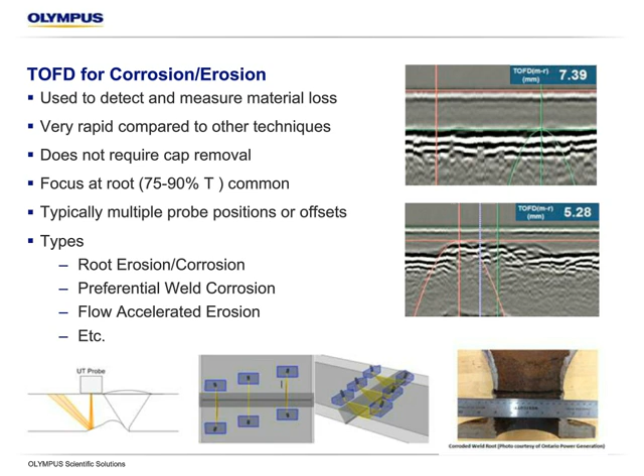So some things to consider when you look at TOFD equipment and what you need. Obviously, what techniques you're going to use, just TOFD or phased array. What channels are required? Do you need a single channel because you're only doing smaller thicknesses, or do you need multi-channels of TOFD to do multi-TOFD? Obviously, the individual equipment characteristics like signal quality, the amount of voltage, its pulse repetition frequency, things like portability and durability for the environment you work in. How long does the battery last? A lot of important features like, does the software offer unique TOFD features that make the acquisition and analysis easy?